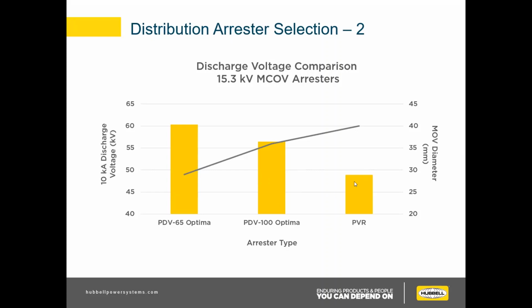And this carries the same trend in our station class. Just a little tidbit here: we have a couple different products that use a 56 millimeter block up to a 75. So the larger the block, the lower the discharge voltage.